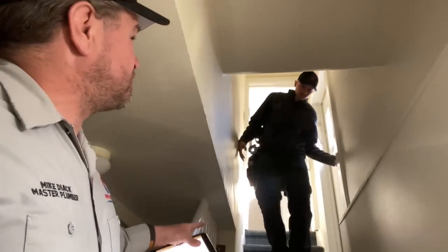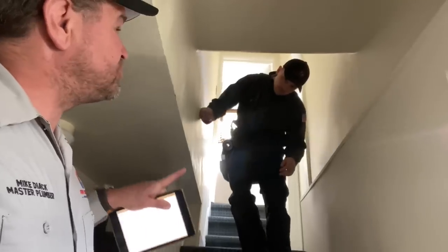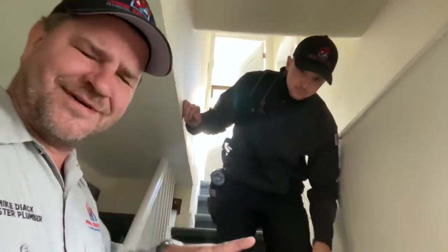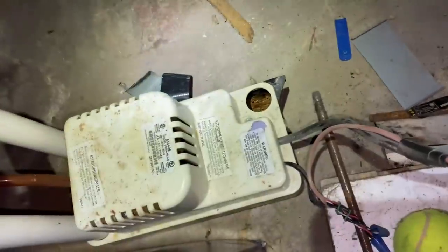All right Peter, so I turned the thermostat on, it's set to cool, there's no action. What we could do first is check for 24 volts, but let's go straight to the air handler since it's accessible. So here's the evaporator, we have a float switch here, wired into a condensate pump, which also looks dry.